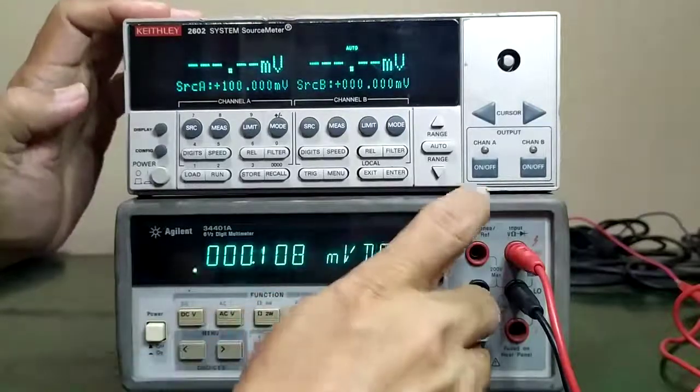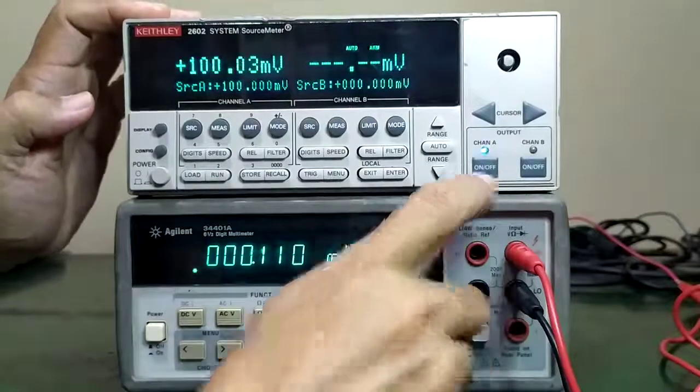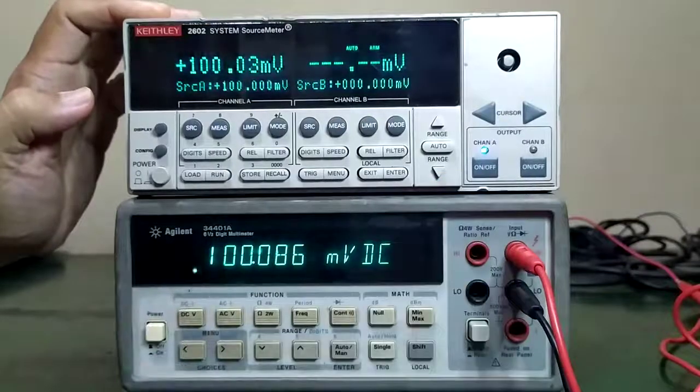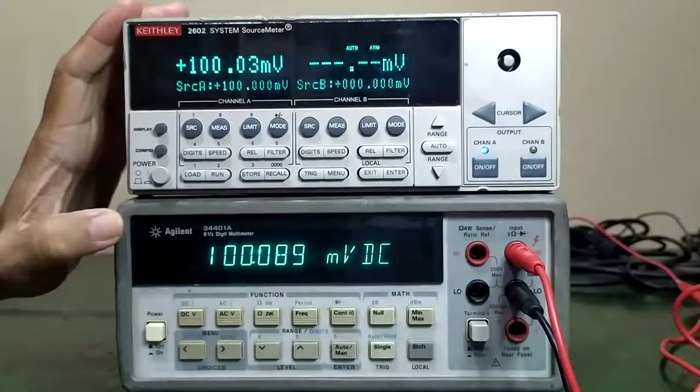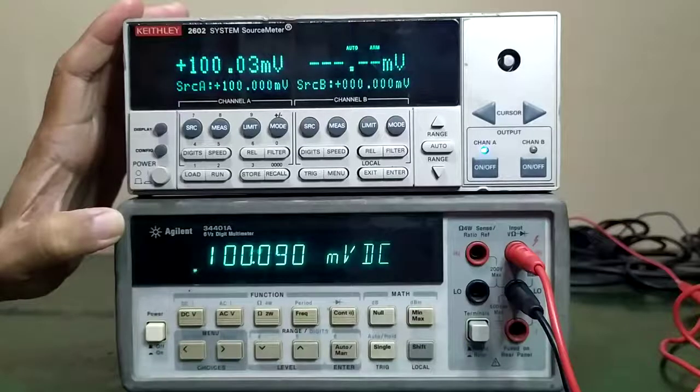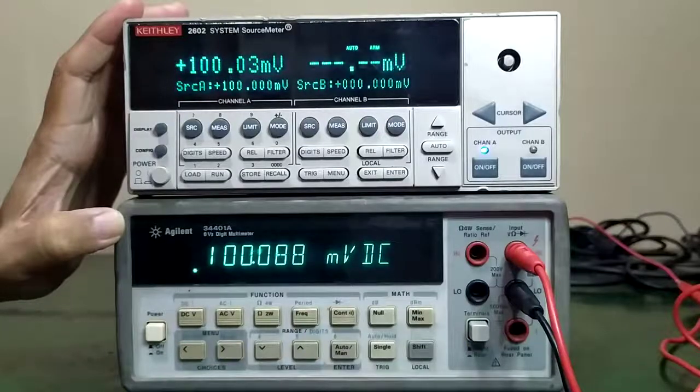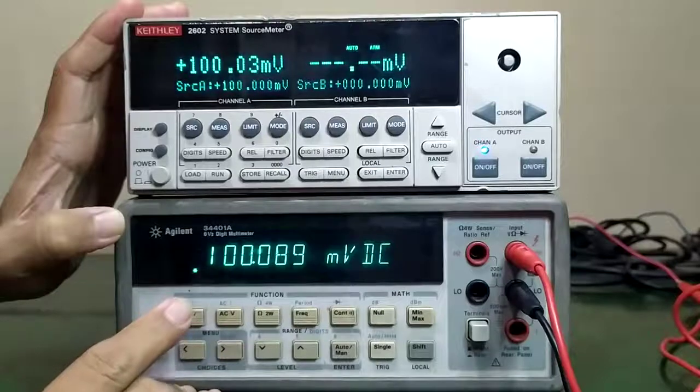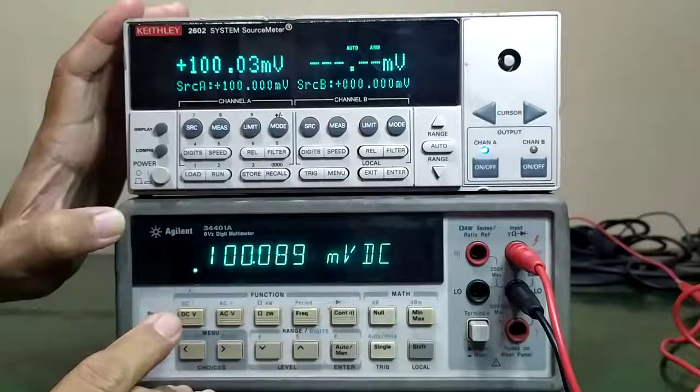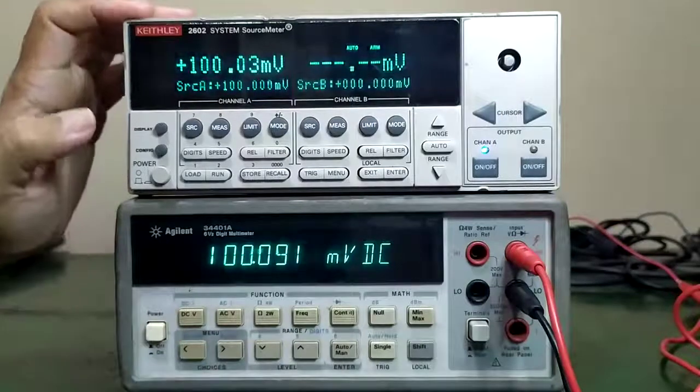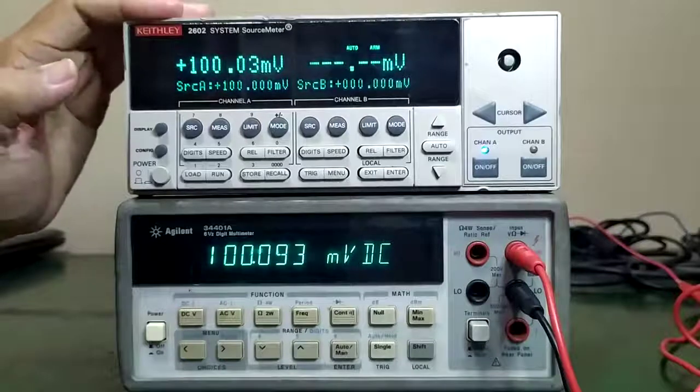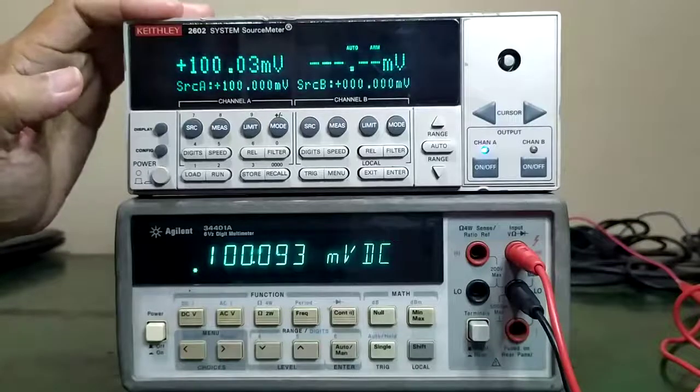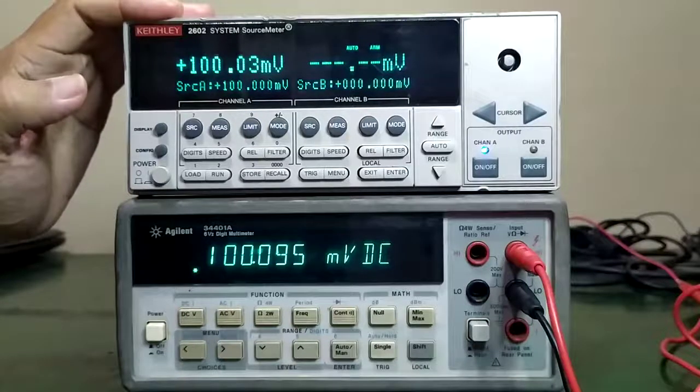We will output 100 millivolts into Channel A. We will use our reference multimeter, Agilent 34401A. We have approximately 100 millivolts DC, and then we measure also approximately 100 millivolts.